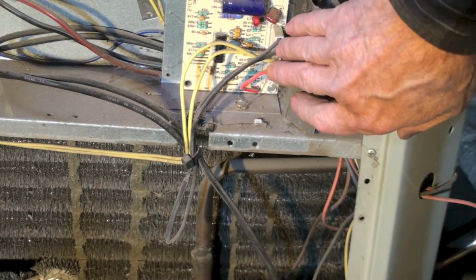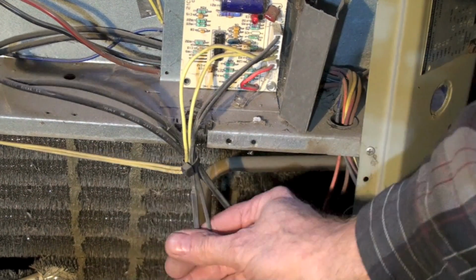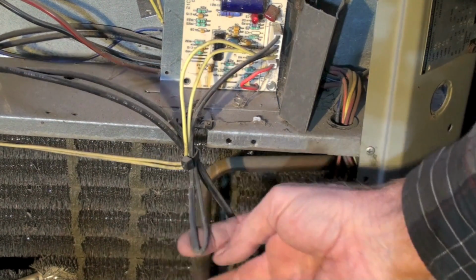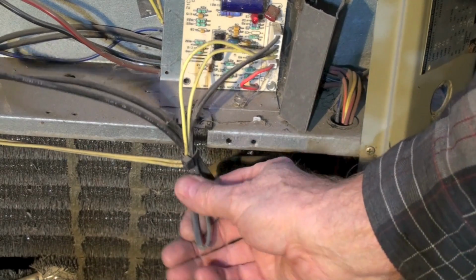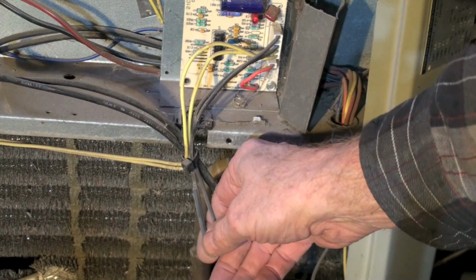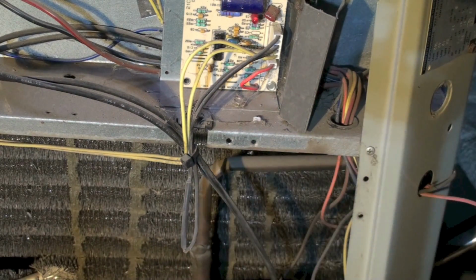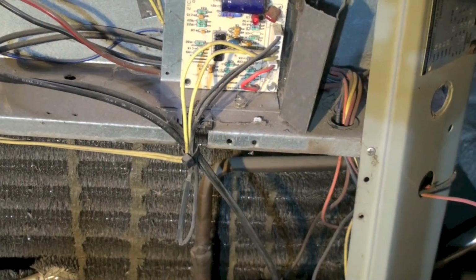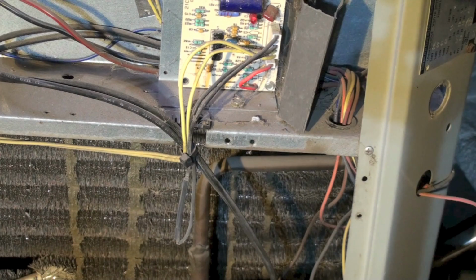Okay, we've got two probes coming off here. One of them's actually right here. That is the probe, an outside air temperature probe. So it's supposed to just detect the outside air. The yellow one, and I'll show you where it goes here in a minute, is to sense the coil temperature.